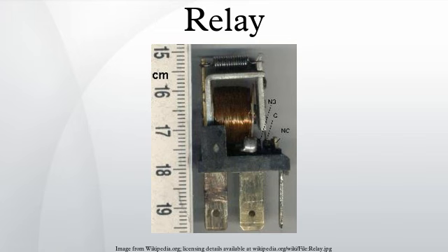When an electric current is passed through the coil, it generates a magnetic field that activates the armature, and the consequent movement of the movable contact(s) either makes or breaks a connection with a fixed contact. If the set of contacts was closed when the relay was de-energized, then the movement opens the contacts and breaks the connection, and vice versa if the contacts were open. When the current to the coil is switched off, the armature is returned by a force, approximately half as strong as the magnetic force, to its relaxed position.